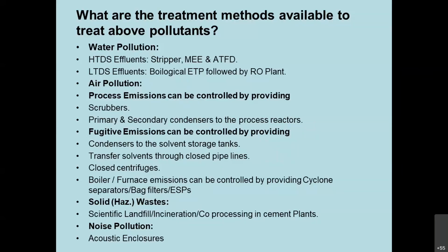So, if the TDS levels are less than 5000 milligram per liter, then it is considered a low TDS effluent. Then it is treated in a biological effluent treatment plant followed by a reverse osmosis plant. Please remember one thing here: if the TDS levels are more than 5000 milligram per liter, then a biological ETP is not suggested. By using a biological ETP, we will not remove the TDS; we will only reduce the BOD and COD levels. These are the techniques to handle high TDS and low TDS.